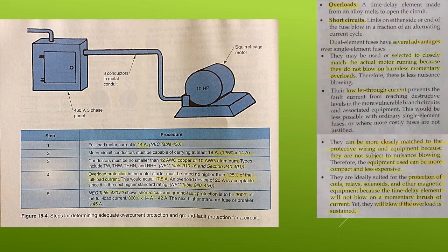Also, they can be more closely matched to the protective wiring and equipment because they are not subject to nuisance blowing. Therefore, the equipment used can be more compact and less expensive. Finally, they are ideally suited for the protection of coils, relays, solenoids, and other magnetic equipment because the time delay element will not blow on a momentary inrush of current. Yet, they will blow if the overload is sustained.